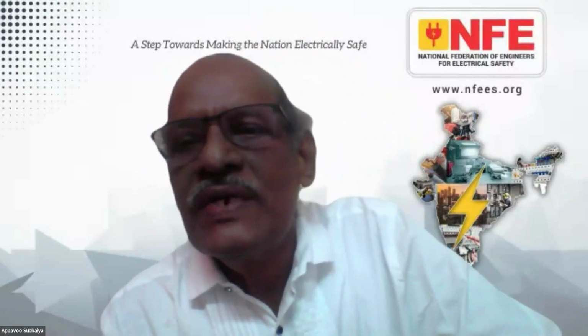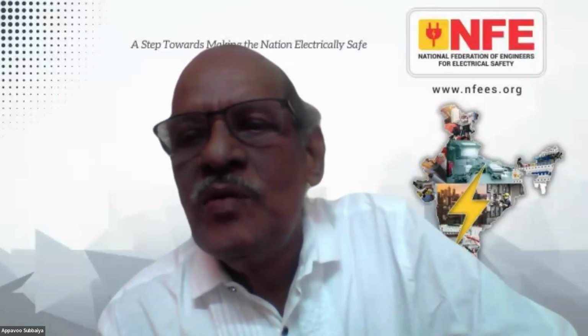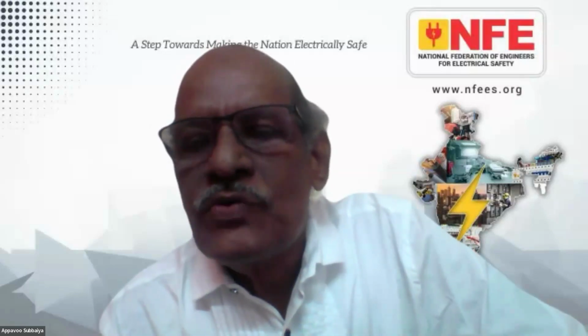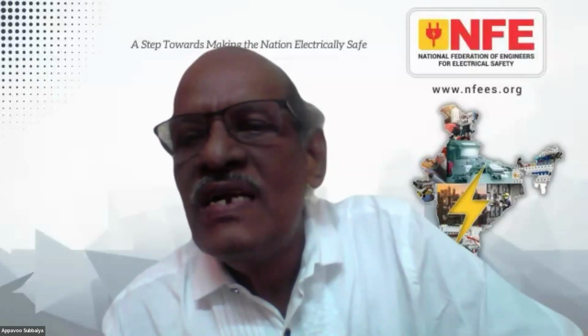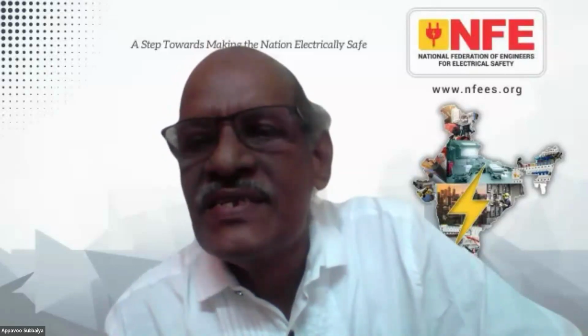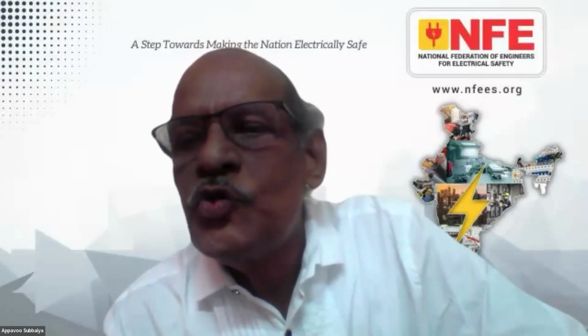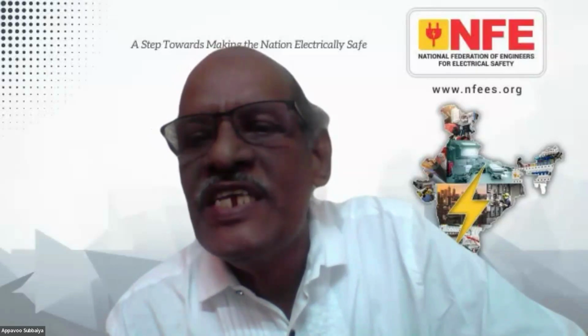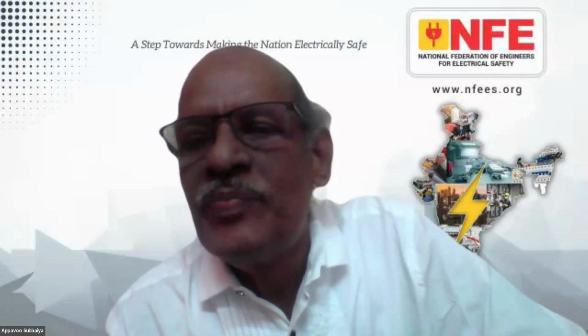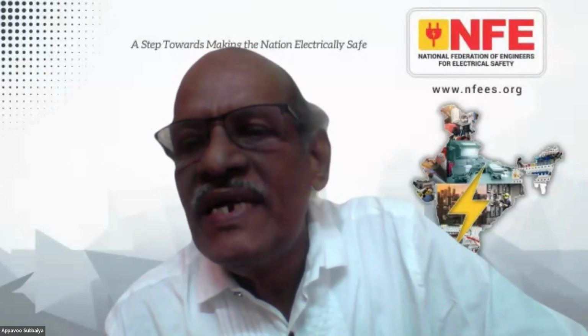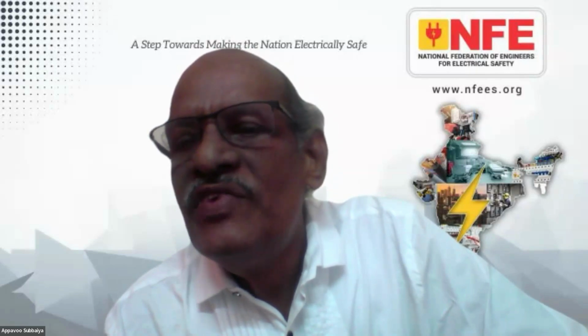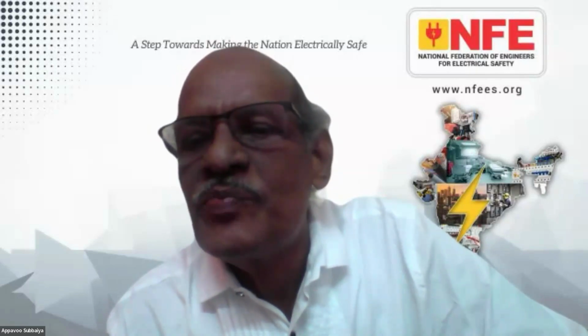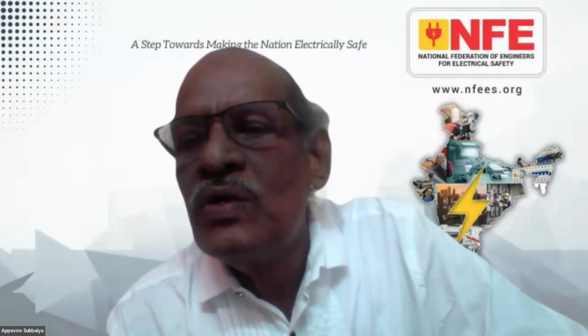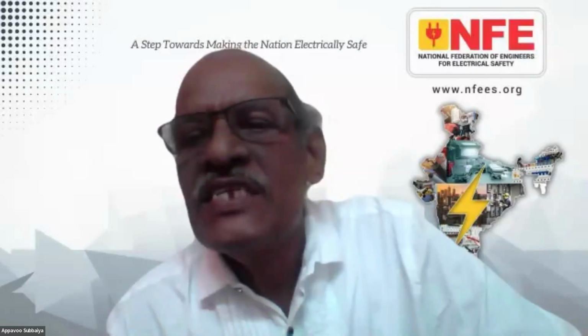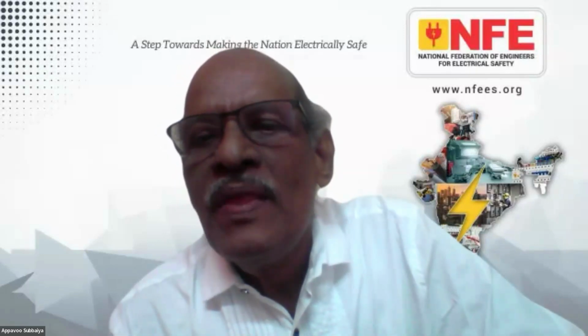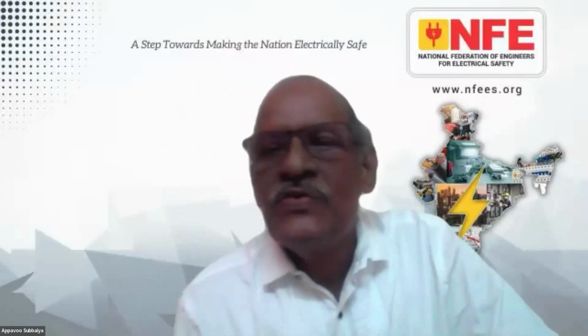Next, another query from Mr. Rajaram Bhatt: if we consider a front access panel with the ACB breaker installed, should there still be a minimum 750 mm rear access for the panel? There are upgraded panels where we can terminate cable and access the breaker from the front without rear access. There's also a related question from Sunil Kumar VK. Mr. Abhijit, can you address this?